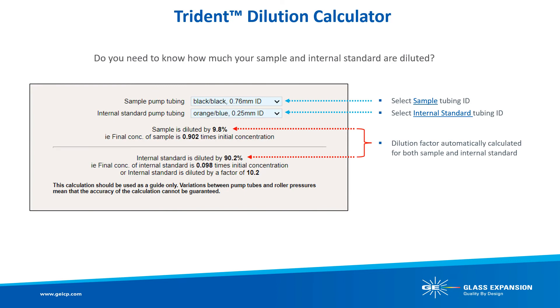Glass Expansion's dilution calculator helps you quickly determine the dilution factor when using the Trident inline reagent kit based on the peristaltic pump tubing installed. In this example, we selected black-black tubing with an internal diameter of 0.76 mm for the sample and orange-blue tubing with 0.25 mm ID for the internal standard, resulting in approximately 10% sample dilution. You can use the drop-down menu to select various tubing combinations and easily calculate your desired dilution factor.